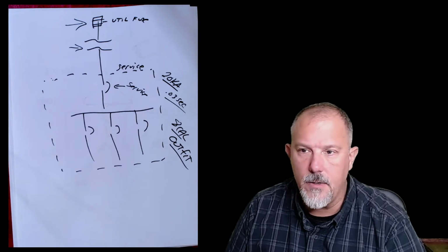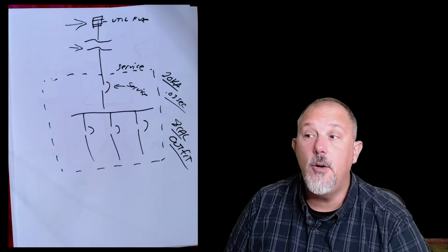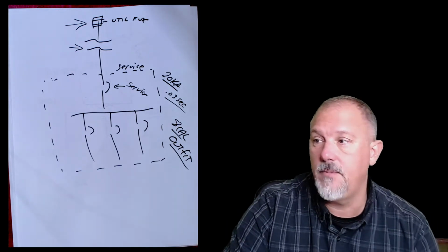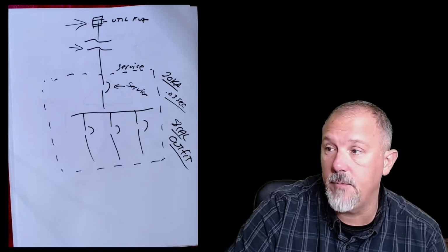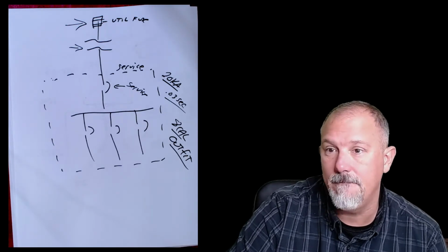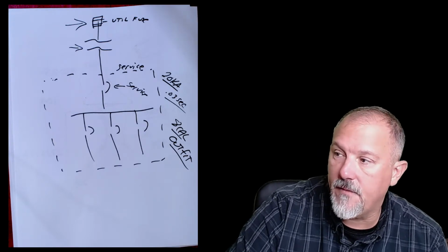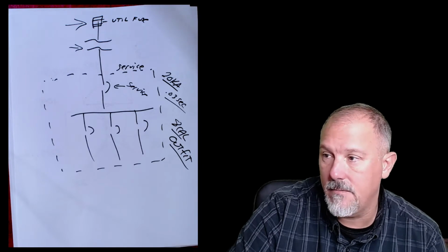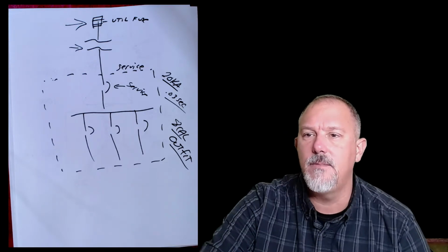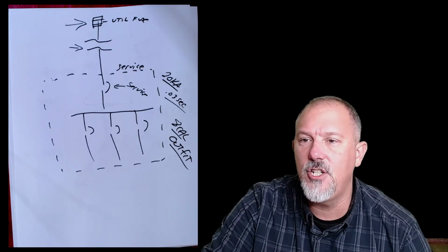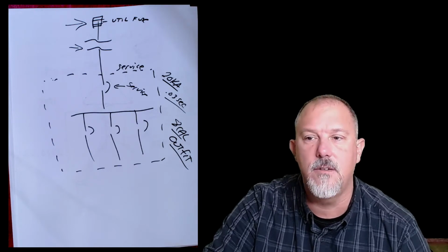70E doesn't say, right? What does the label have to say? B does not tell me. No, B doesn't tell you, but it tells you that it has to be in accordance with acceptable industry practice. And there's an informational note that says NFPA 70E, standard for electrical safety in the workplace, for acceptable industry practice for equipment labeling. So 70E 2021, I get into discussions with AHJs. Most always, no, I'm willing to listen. AHJs are not willing to talk.